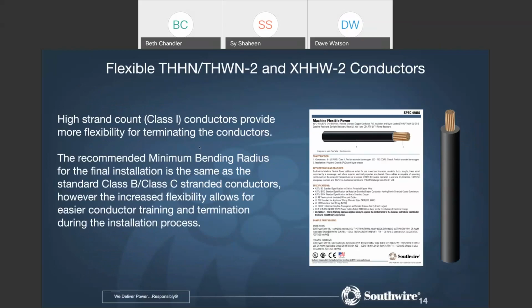I earlier alluded to the fact that we have flexible versions of the THHN and XHHW, and I believe we said the RHW USE product as well. These flexible conductors are a high strand count, Class I conductors. They're made with a different type of stranding, like a rope lay stranding, with much smaller strands. This is going to make a product that's easier to bend. Now, the recommended minimum bending radius for the final installation is still going to be the same as the standard stranding classes for these products, which are the Class B and Class C strandings. These are made with a fewer number of, larger strands. So you're still going to have that same minimum bending radius.